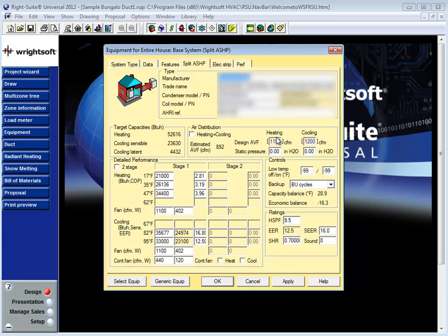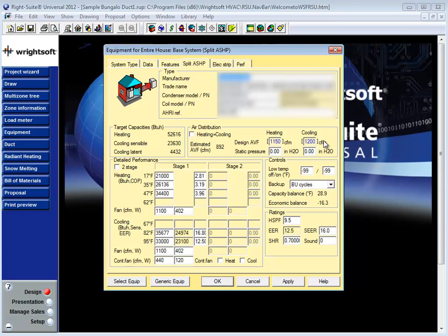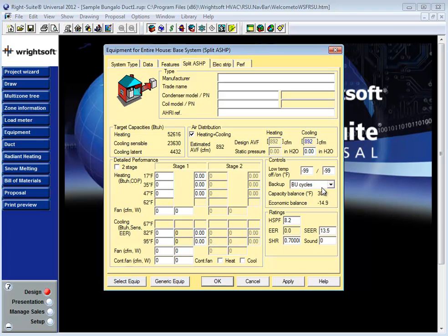In other words in order to have the right amount of sensible and latent cooling from this heat pump I'm going to need 1200 CFM moving through this system. Now unfortunately at the time of this recording none of the manufacturers who are providing their extended performance data are also providing static pressure data so I'm going to be responsible for determining at what static pressure this fan can deliver 1200 CFM at the desired fan setting that I'm going to design for.